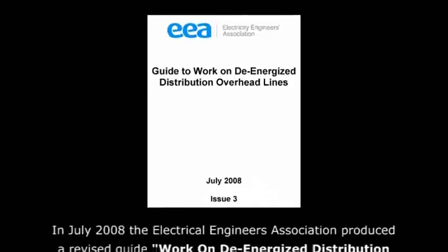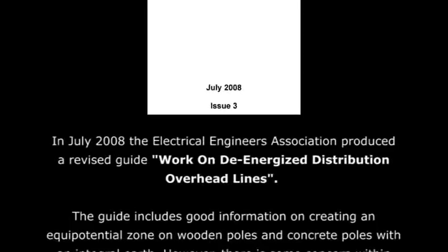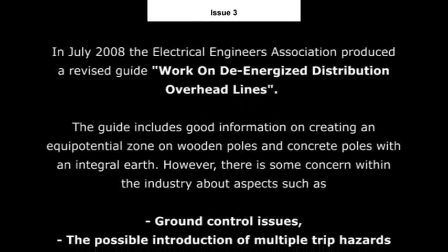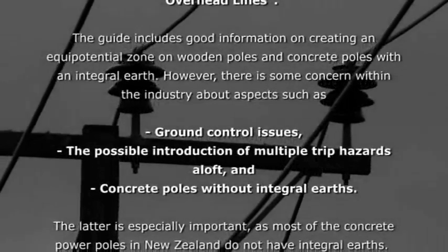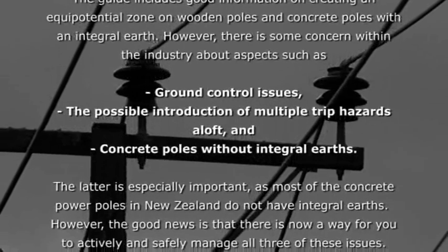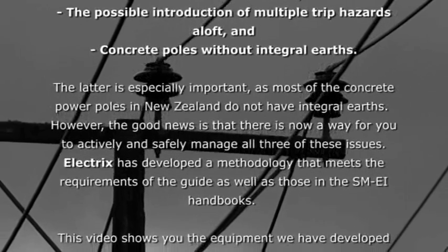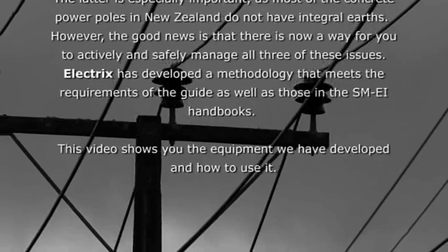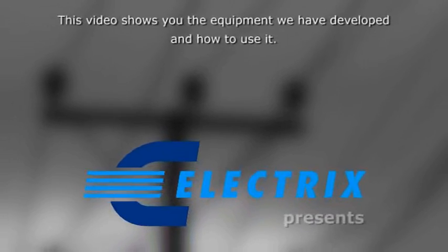In July 2008, the Electrical Engineers Association produced a revised guide: Work on De-Energized Distribution Overhead Lines. The guide includes good information on creating an equipotential zone on wooden poles and concrete poles with an integral earth. However, there is some concern within the industry about ground control issues, the possible introduction of multiple trip hazards aloft, and concrete poles without integral earths. The latter is especially important, as most concrete power poles in New Zealand do not have integral earths. The good news is that there is now a way to actively and safely manage all three of these issues. Electrix has developed a methodology that meets the requirements of the guide as well as those in the SMEI handbooks. This video shows you the equipment we have developed and how to use it.